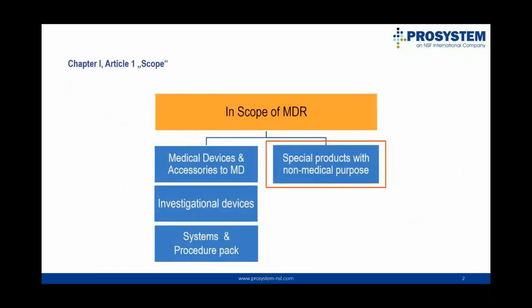Let us get started and jump into the scope discussion of the new regulation. The MDR is a legal document of over 175 pages, and it subsequently follows the current rules of a directive, the Medical Device Directive, and the Directive of Active Implantable Medical Devices. So when we look into the chapter of definitions in the new MDR, we will see that key terms like medical device or accessories have been slightly modified. So the definitions are different than in existing regulations.